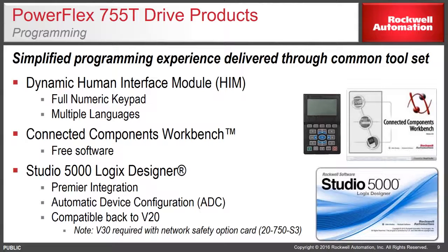The PowerFlex 755T simplifies programming through common tools. It uses a dynamic human interface module, which is a full numeric keypad with multiple language support. It also can be programmed via Connected Components Workbench, which is free software. It also can be programmed via Studio 5000 Logix Designer using Premier integration with features like automatic device configuration. All of this is compatible back to version 20. However, if safety over Ethernet is required, you need version 30.